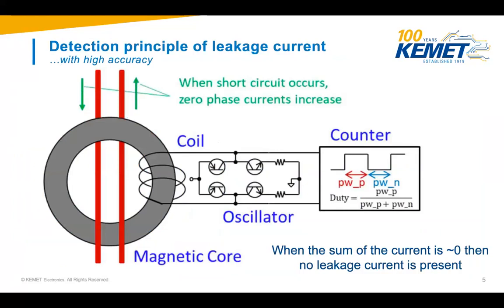With an AC leakage, you usually have the 50 hertz or 60 hertz, whatever your supply frequency is, detected by the coil. Usually how many conductors you have through the magnetic core doesn't really matter. When you have all of those supplying the application, the zero phase current should be zero, so there should be no leakage, because everything that current goes in should go out as well as usual. Whether you have one phase and one neutral, or three phases and one neutral, it doesn't matter.